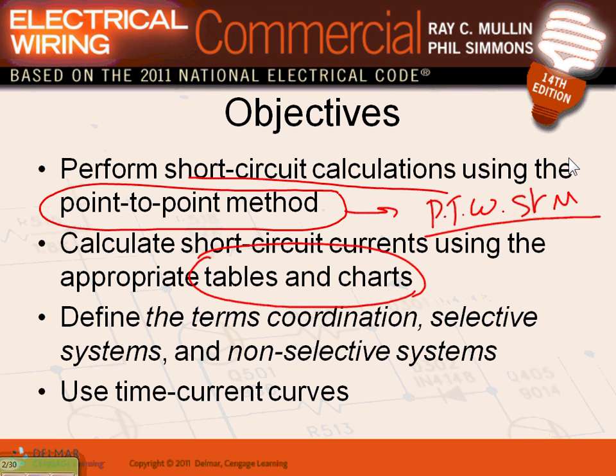And then based on this, we do the coordination, guys, selective and non-selective system. By now you know what a selective system is. In a fully selective system, if I have a short circuit in this branch circuit right above your head, I want this circuit breaker to trip, not the circuit breaker that feeds this panel. We'll talk about the selective coordination, and to do the selective coordination, we have to do time current curves. We looked at these yesterday. The higher the current, the faster the system will trip.